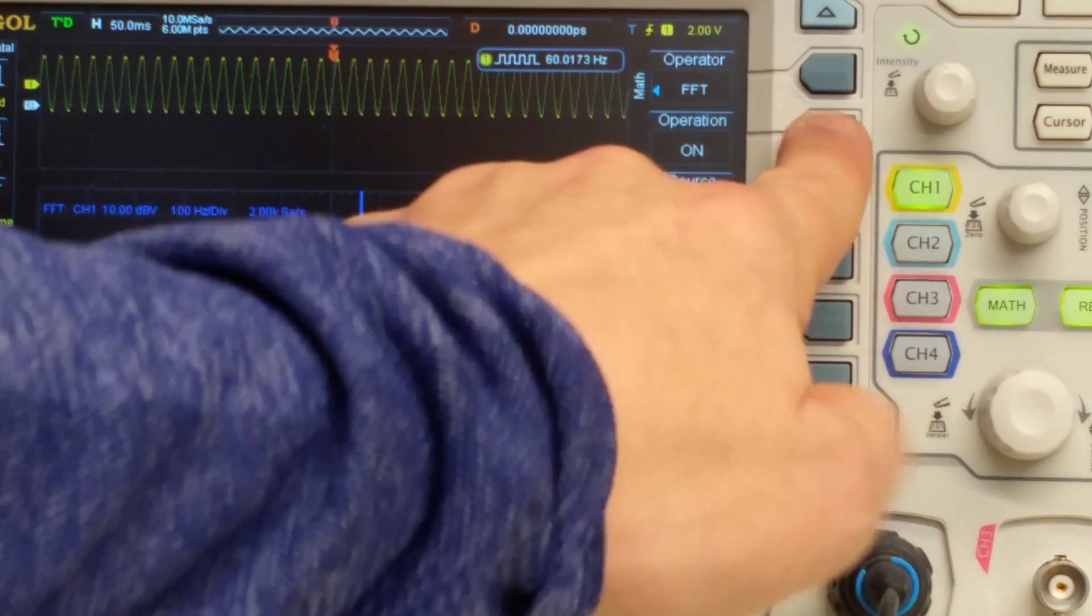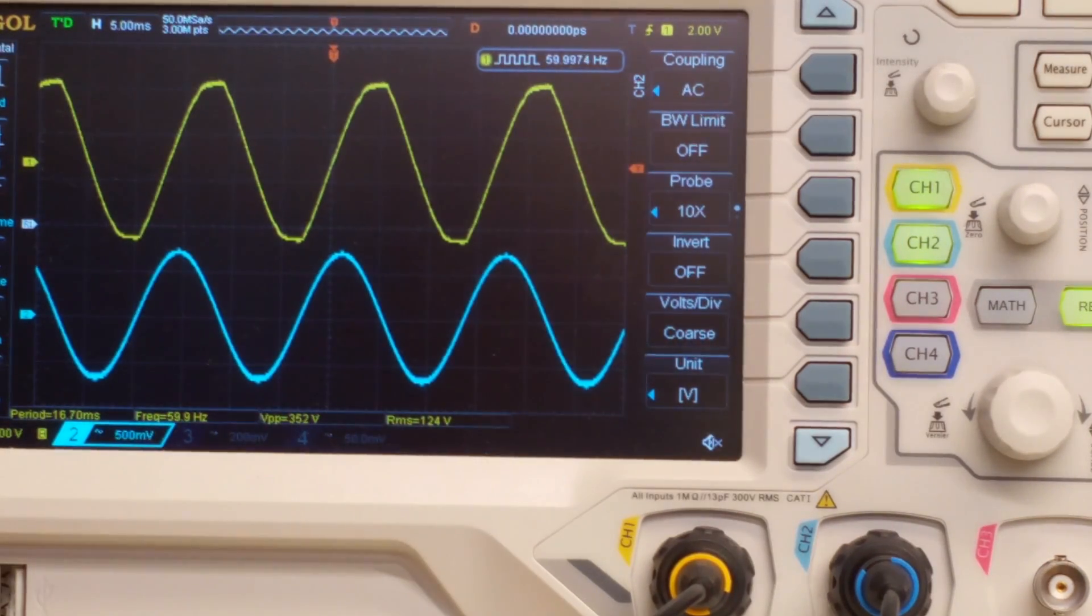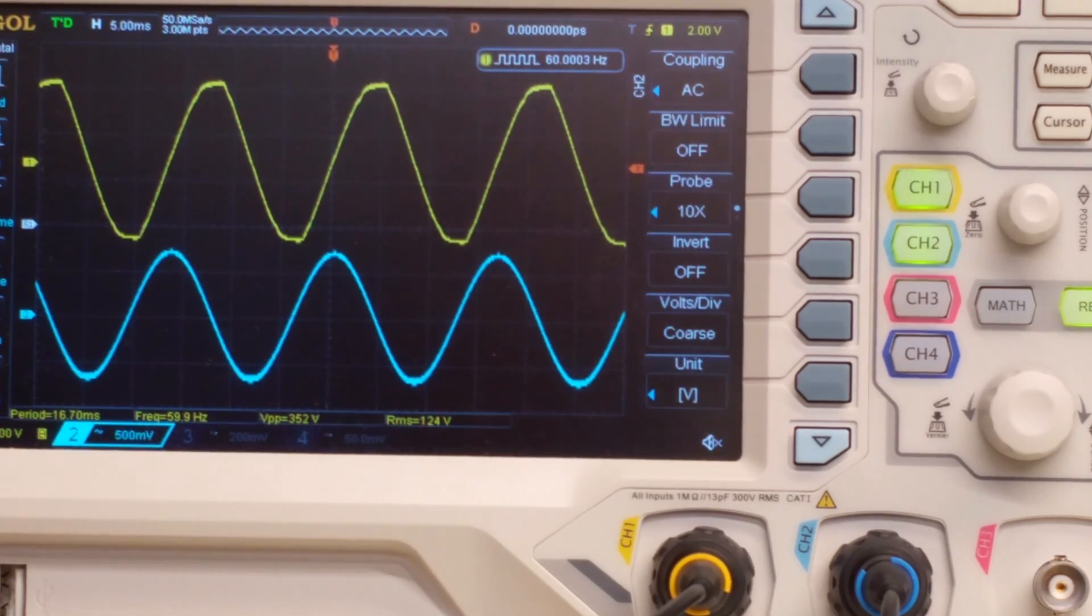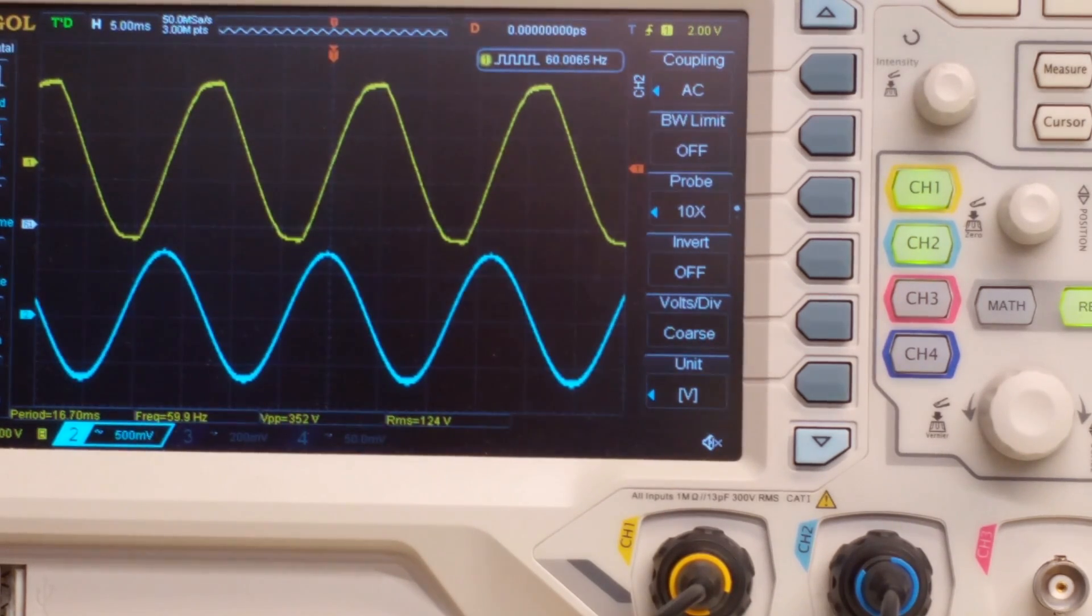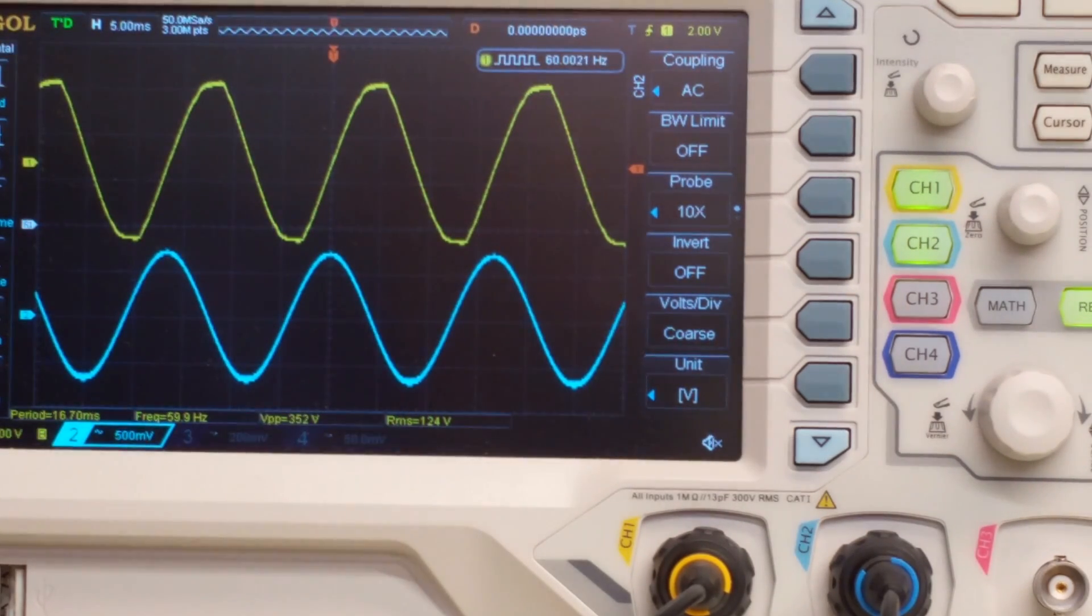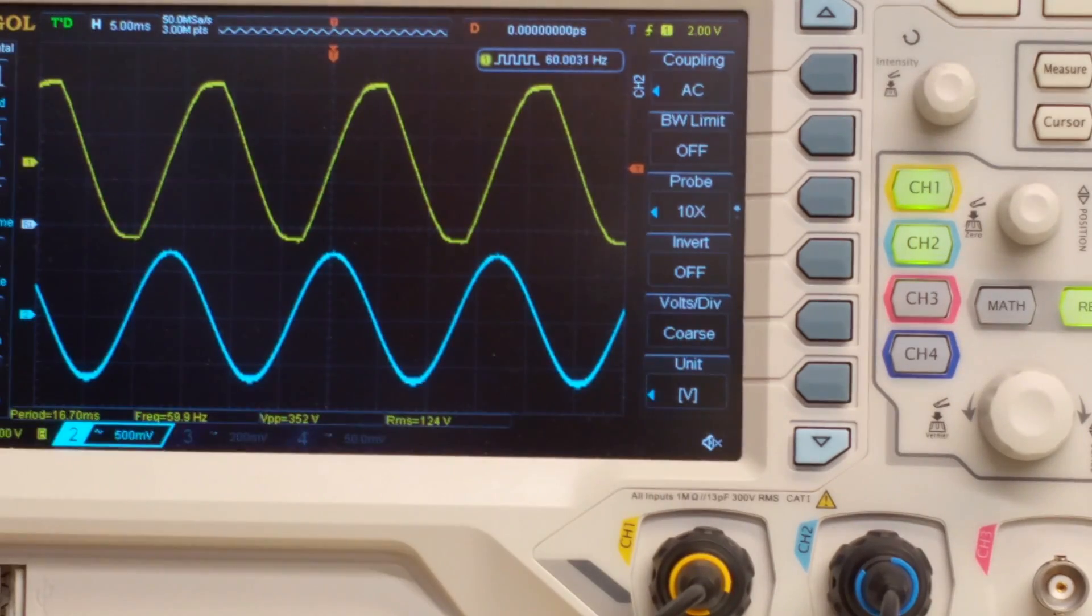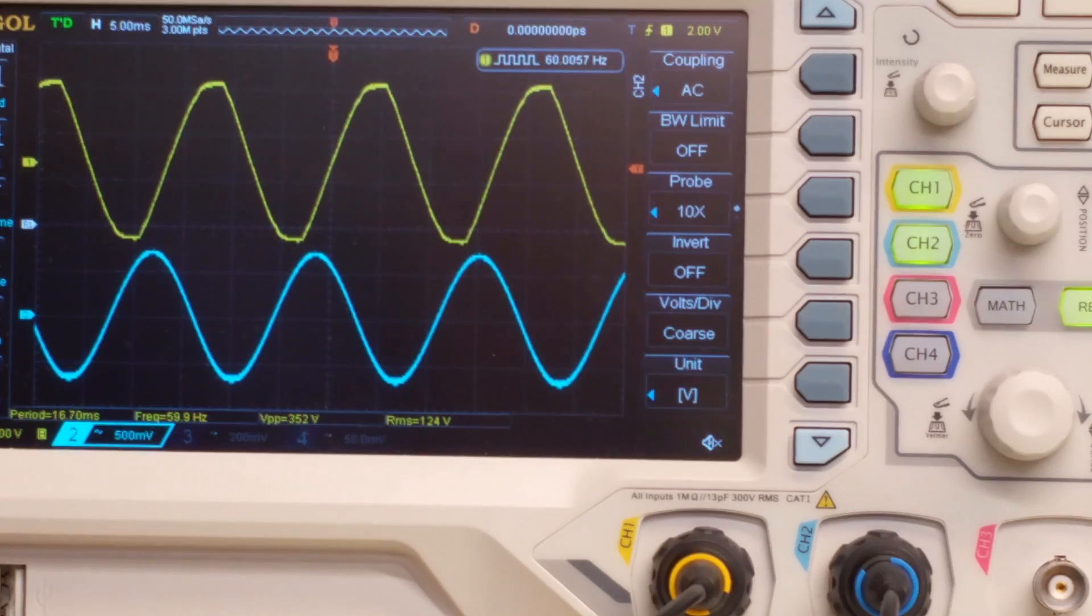So this is not at all what you would expect, what I would expect anyway, from the frequency domain. I would expect, if it were pure sinusoid, you should have a 60 hertz spike. And if you had a little bit of the first harmonic, then you would have a spike at 120 hertz, not 180 hertz. 180 hertz is the third harmonic. And then where this 300 hertz feature is coming from is anyone's guess. But at any rate, this is not a pure spectrum. This has a significant amount of undesired features. And that really is why we see this very unsinusoidal waveform in the power line.